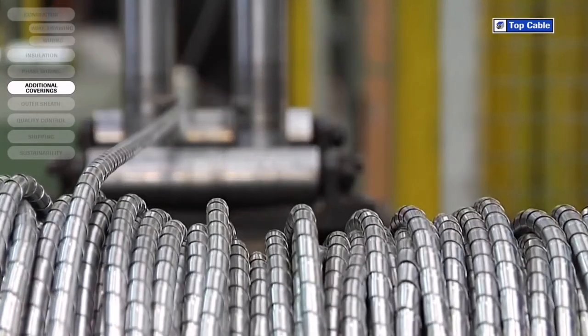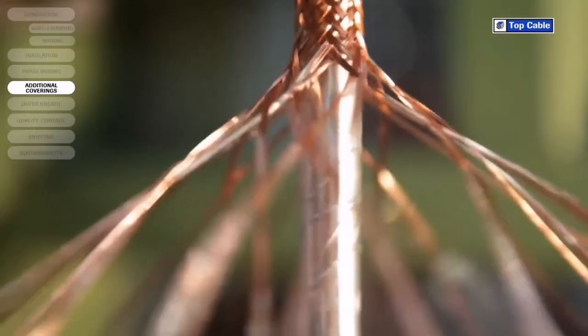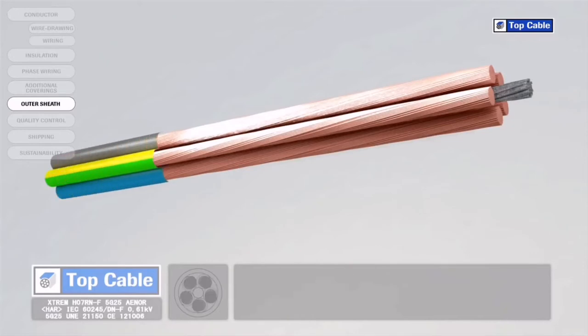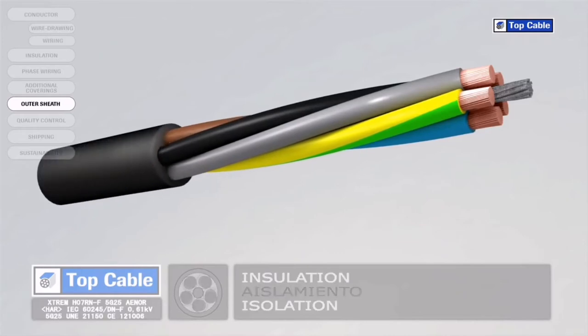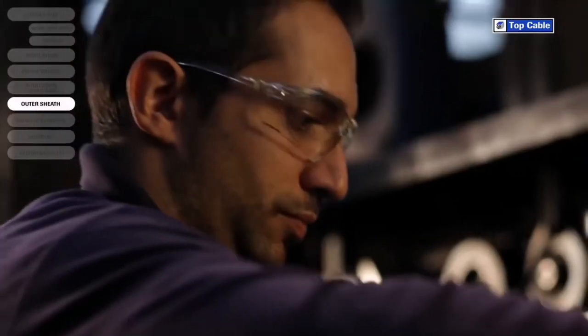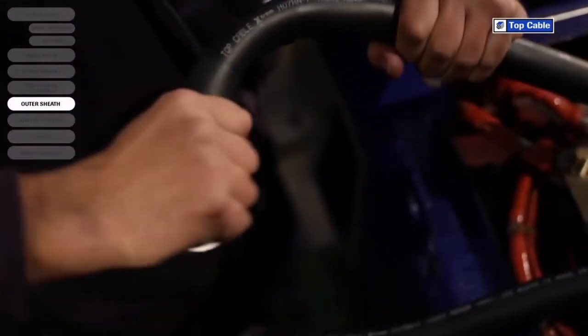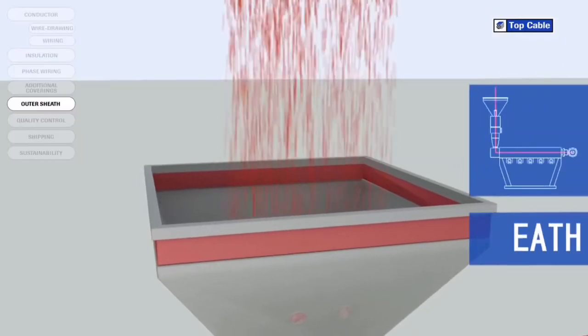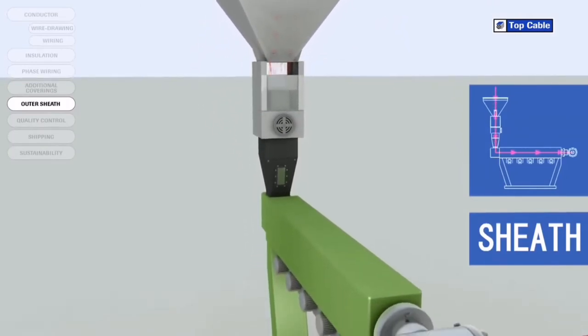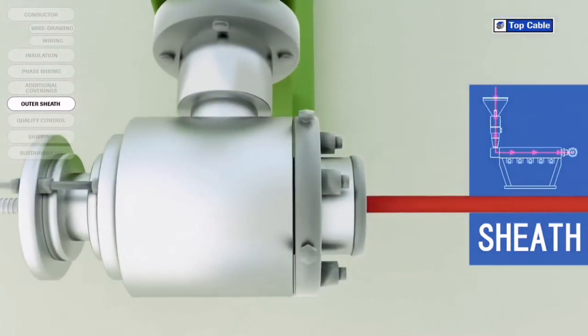The armor is made from steel or aluminum and can come in the form of metal strips, wires, or braids. Cables usually have an outer polymer covering for protection, called the outer sheath. The sheath protects the conductors and their insulation from external elements which may change their electrical properties, such as moisture. It also protects them from mechanical aggression which may occur during installation. As with the insulation, the outer sheath can be made from a thermoplastic or a thermosetting plastic, and is applied via a process of extrusion at high temperature. The sheath material may vary depending on the required protection level, the final flexibility of the cable, the work environment, etc.